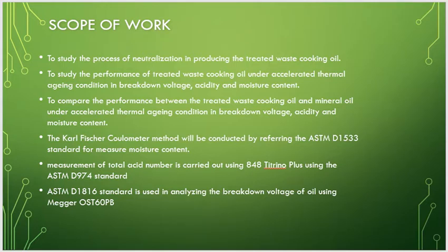Next, for the scope of work, the Karl Fischer Coulometer method will be conducted by referring to the ASTM D1533 standard for measuring moisture content. Measurement of total acid number is carried out using the 848 Titrino Plus using the ASTM D974 standard, and the ASTM D1816 standard is used in analyzing the breakdown voltage of oil using the Megger OST60PB.